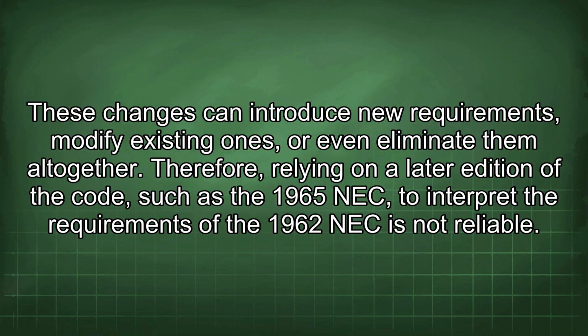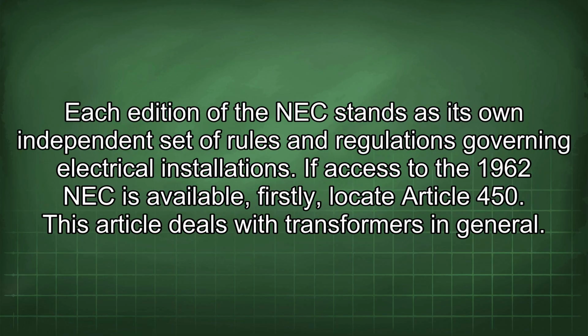Therefore, relying on a later edition of the code, such as the 1965 NEC, to interpret the requirements of the 1962 NEC is not reliable. Each edition of the NEC stands as its own independent set of rules and regulations governing electrical installations. If access to the 1962 NEC is available, firstly, locate Article 450. This article deals with transformers in general.